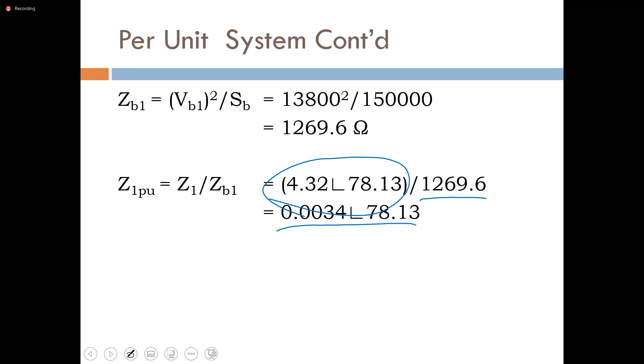The purpose is that the per unit value going across the transformer remains the same. So if I have my one-line diagram, I can now just add the reactances if they are connected in series, even when I'm crossing a transformer, because regardless of which direction I'm going, where the transformer is concerned, the per unit reactance remains the same. So Z1 per unit equals Z2 per unit.